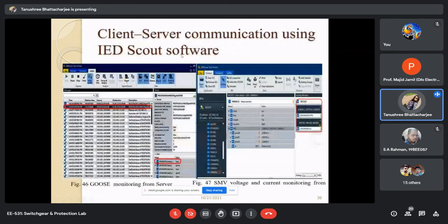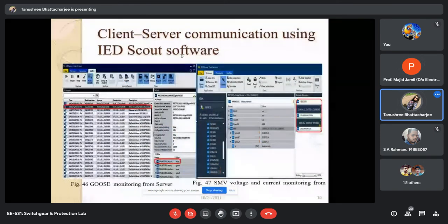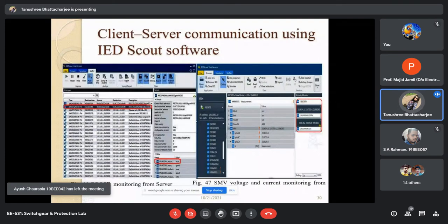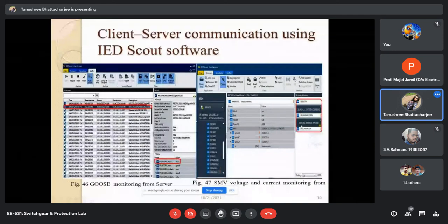Now coming to the two PCs which we have installed, a client PC and a server PC. We can now monitor GOOSE values and SMV values from the server PC. This is the GOOSE. It is showing that the GOOSE value has been transmitted and it is true, in the sniffer application of IED Scout. IED Scout is another software, a trial version or licensed version, which you can use in a substation PC to monitor and control other IEDs in a client or remote location. And this is the voltage and current values, or sample measured values, of the REC 670 relay. You can see exactly 219, or approximately 220 kV, and 1 kiloampere we are monitoring from the server PC.